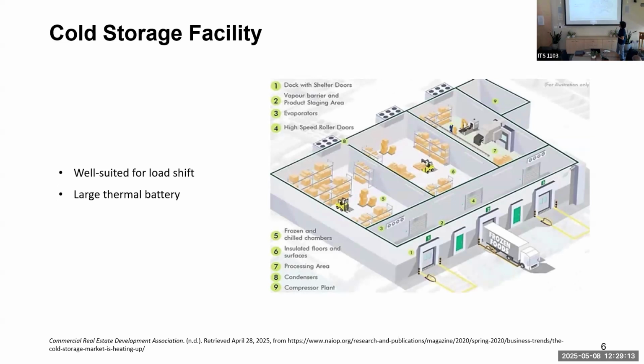Cold storage can be thought of as a large thermal battery, which you can charge during your off-peak periods. So maybe during the early hours of the night, or when a lot of solar is available, you can pre-cool your facility, or cool it down beyond the lower set point that you have. And then when you reach the on-peak period, you can set your set point such that the facility can coast, and you're not drawing power during those on-peak periods. So with this inherent capability to act as a thermal battery, the cold storage facility is a good option to explore demand response and load flexibility.